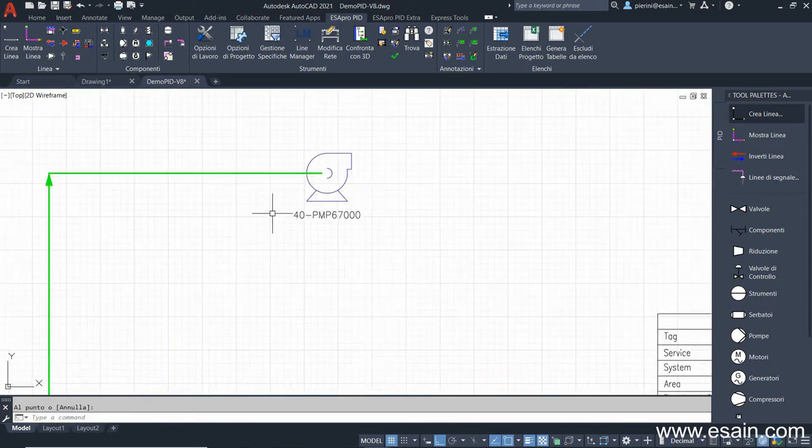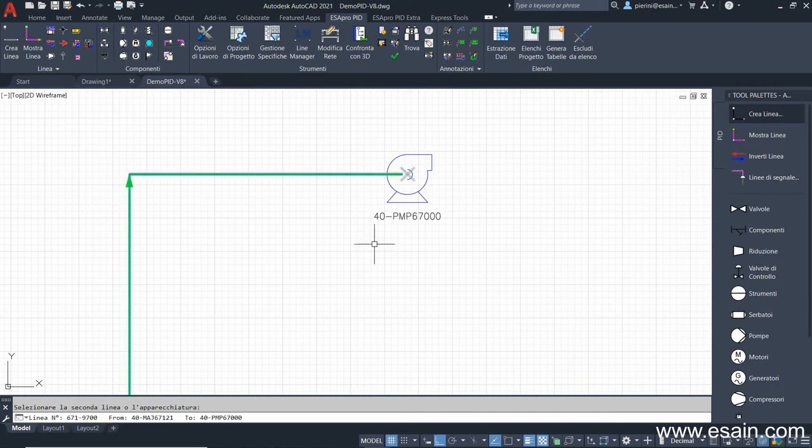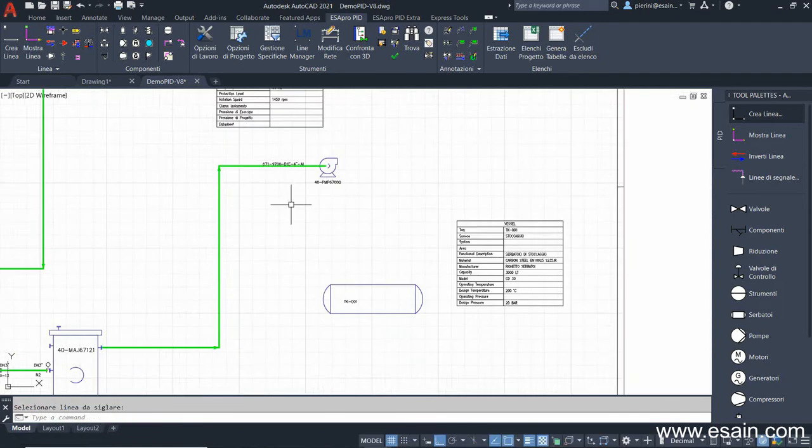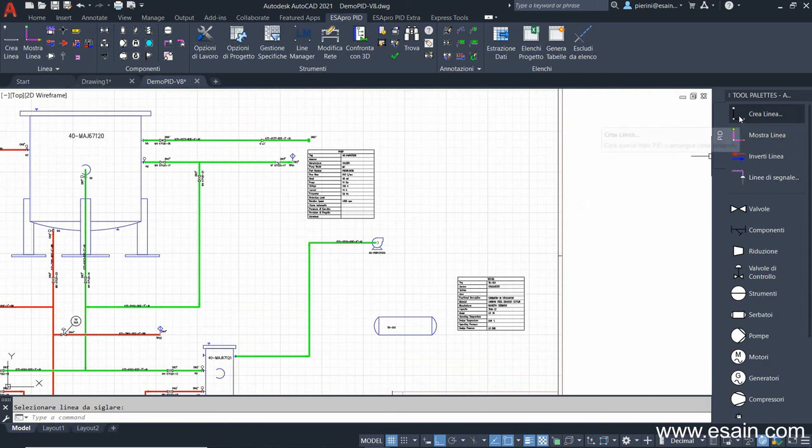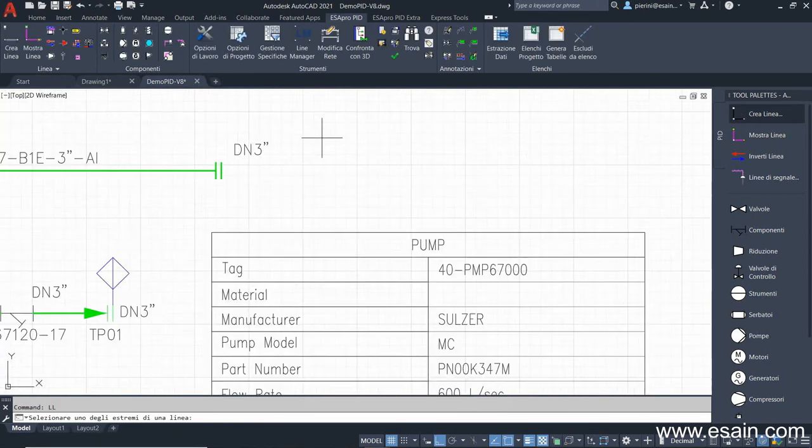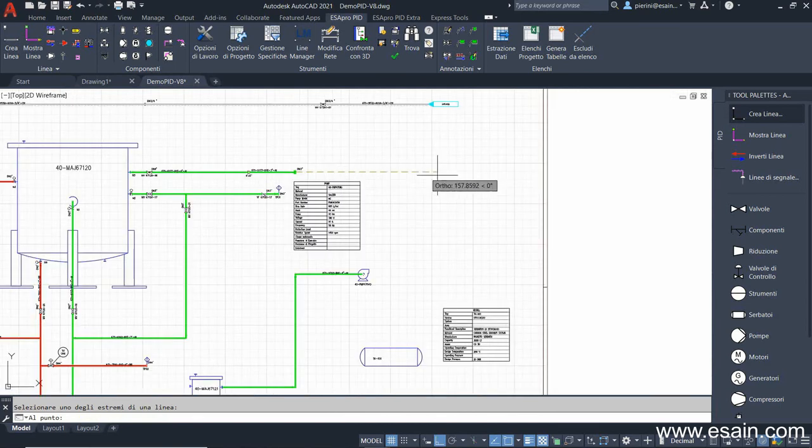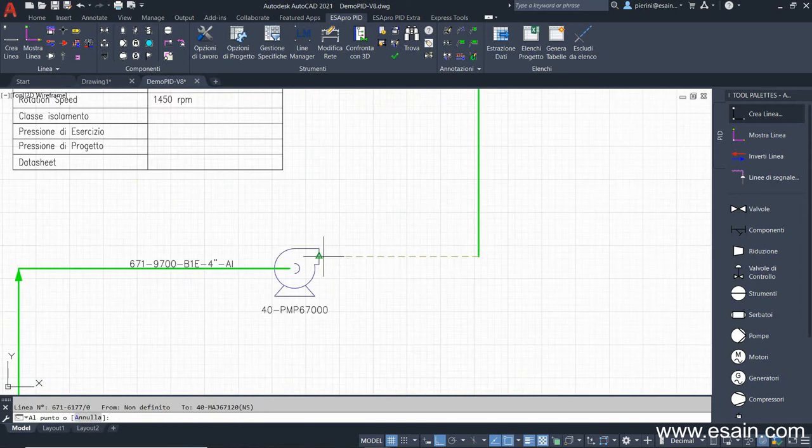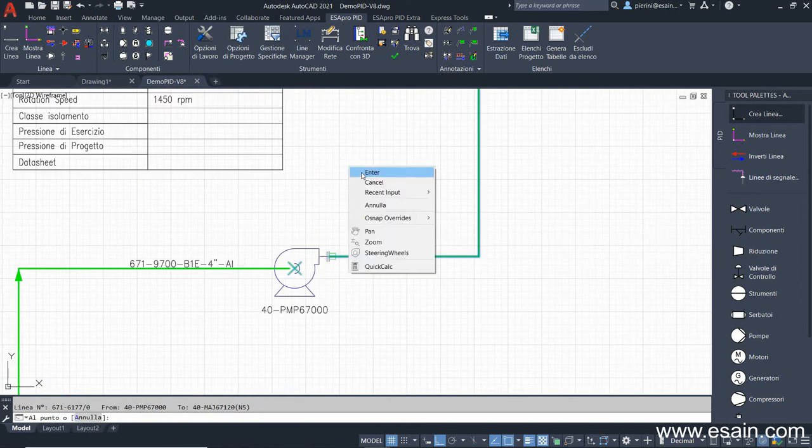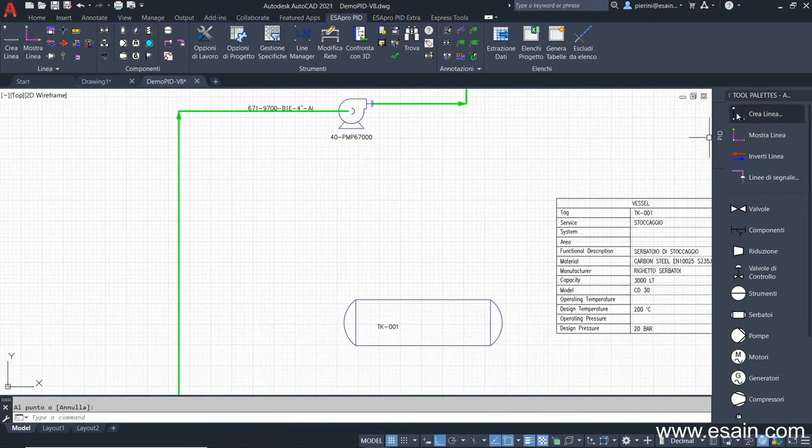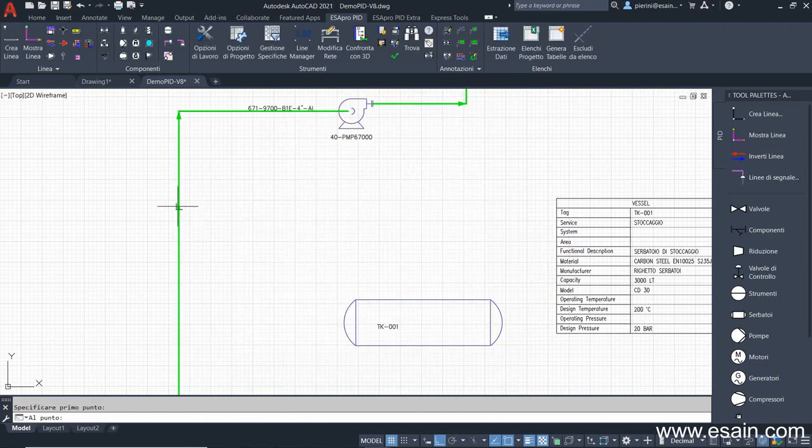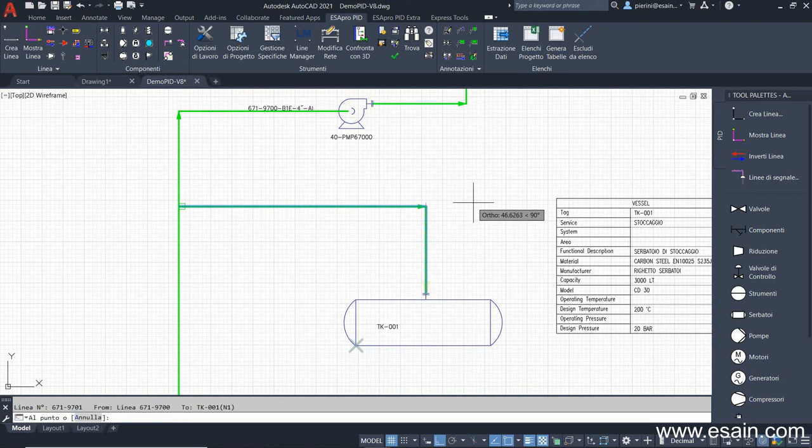Once drawn, this line has a flow sense and connecting information, which are shown on the command line. Through the tag line command, I can tag the line to show the main characteristics. Now let's connect the other lines with continue line. We continue an existing line and connect it to the pump outlet. By doing so, we reuse the same line number. Now let's generate a new line to connect the tank to line 9700. The nozzle is automatically generated.